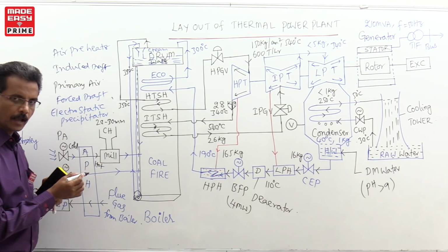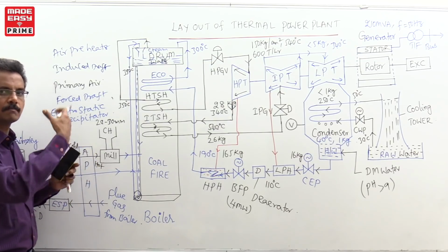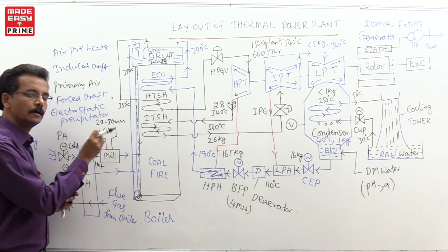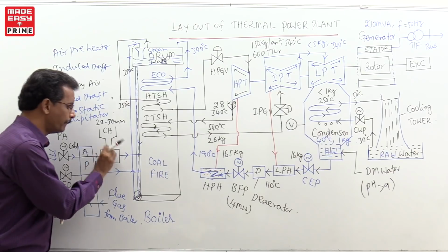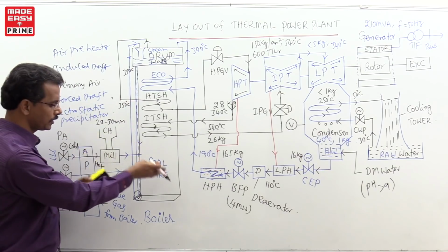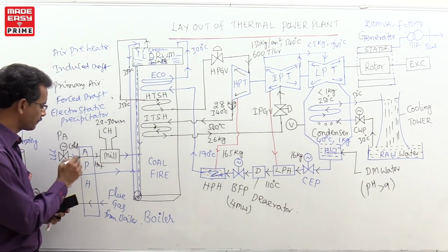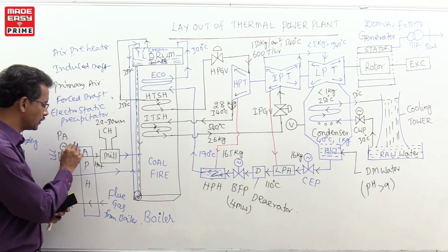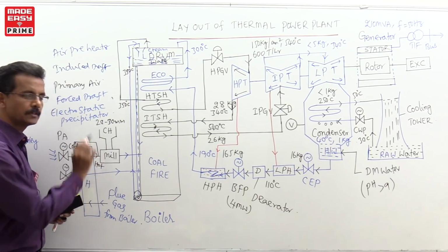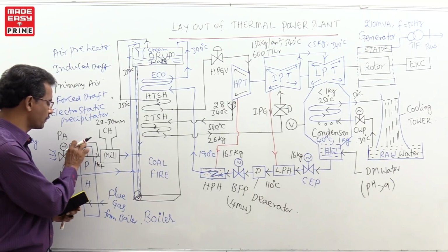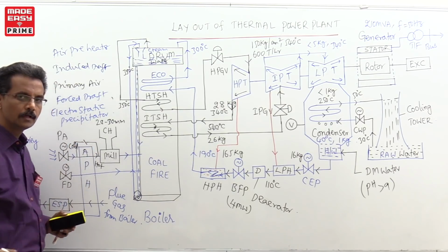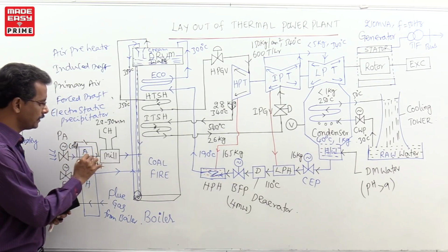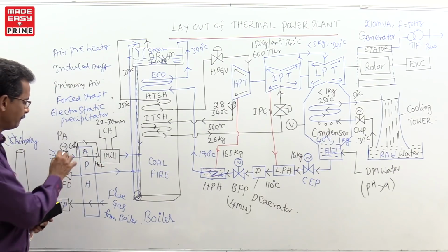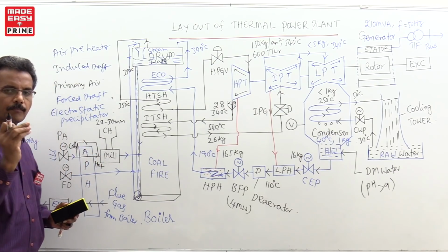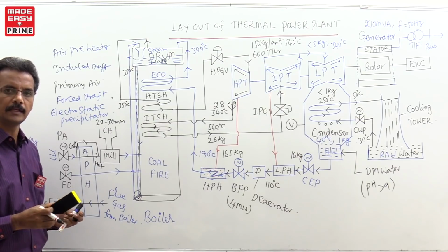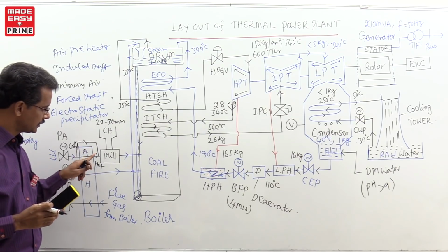Sometimes, if the hot air temperature is much higher, there is a possibility that the coal may burn inside the mill itself before being sent into the boiler. For that purpose, they can mix some part of the cold air with the hot air, not the complete part. They use a simple controller, and by controlling it they mix the cold air with the hot air. The mixing in proportion controls the air temperature.